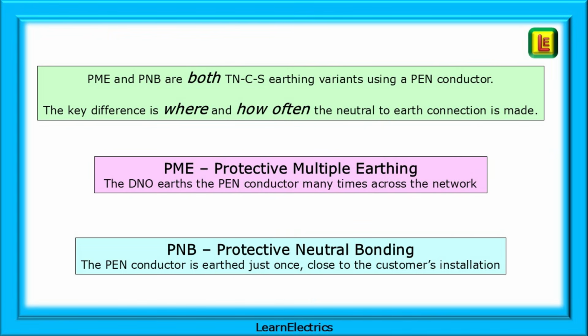There are 4 items that must be understood from the outset. 3 are shown on this page. Number 1, PME and PNB are both TNCS earthing variants using a PEN conductor. The key difference is where and how often the neutral to earth connection is made, as we shall discover.